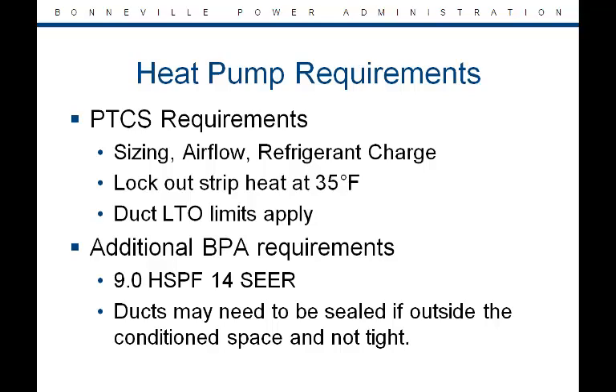As with duct sealing, heat pump reimbursements must meet both the PTCS technical installation standards and BPA program requirements to be eligible for reimbursement. This includes PTCS requirements for sizing, airflow, refrigerant charge, strip heat lockout, and duct leakage, as outlined in the most currently adopted PTCS specification posted on the BPA ResHVAC website. BPA also requires that the heat pump installed has a minimum performance rating of 9 HSPF and 14 SEER, and that the ducts be sealed if they are eligible for the duct sealing measure.